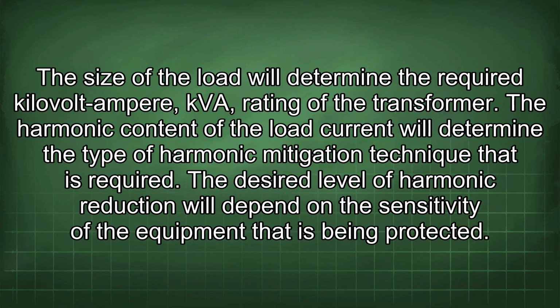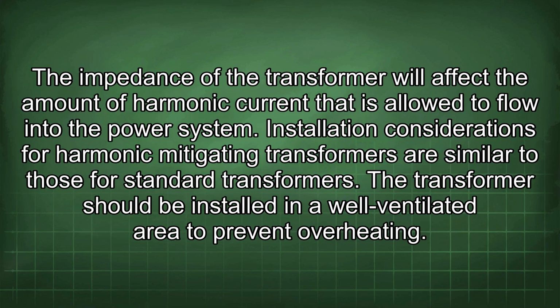The size of the load will determine the required kilovolt-ampere, kVA, rating of the transformer. The harmonic content of the load current will determine the type of harmonic mitigation technique that is required. The desired level of harmonic reduction will depend on the sensitivity of the equipment that is being protected. The impedance of the transformer will affect the amount of harmonic current that is allowed to flow into the power system.